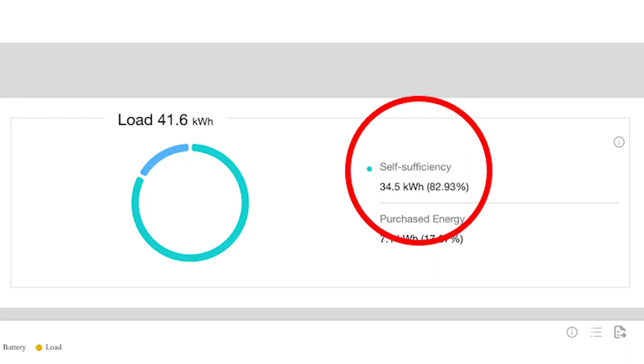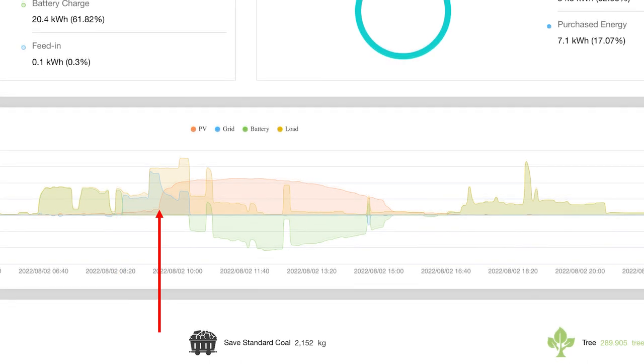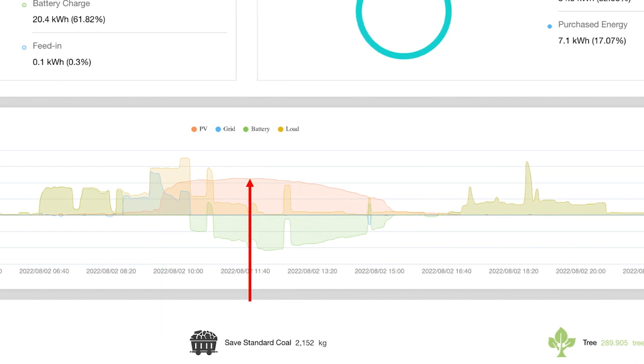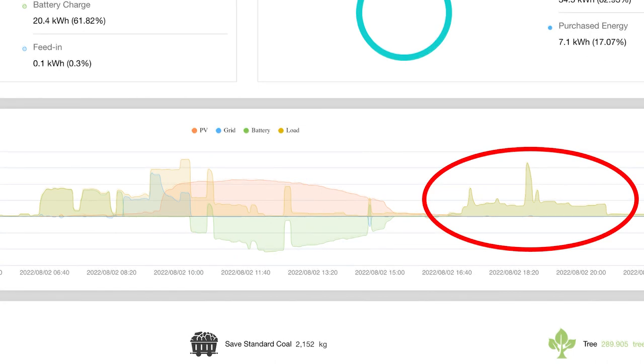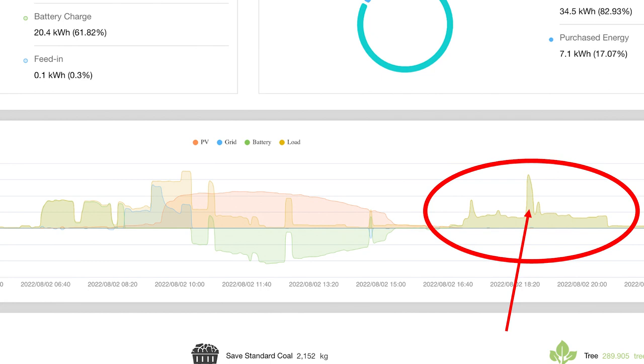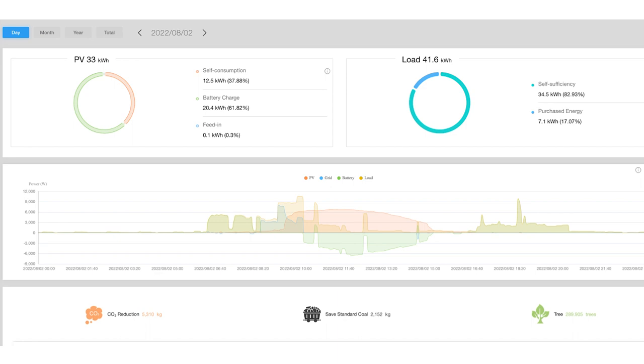From the graph we can see the solar generation curve with a slow increase in the morning, a big kick around 9 a.m., then plateau through the day. You can also see where the load is covered by the battery, with excess flowing into the battery and occasional peaks and troughs where demand increased — the client accessed a little storage around 10:30 a.m. and then continued throughout the day. As we move into the evening when PV generation has ceased, the load is fully covered by the battery. There's even a peak around 6:20 p.m. where over nine kilowatts was supplied from the battery. Around midnight to 1 a.m., the battery was empty and they went back to grid power.